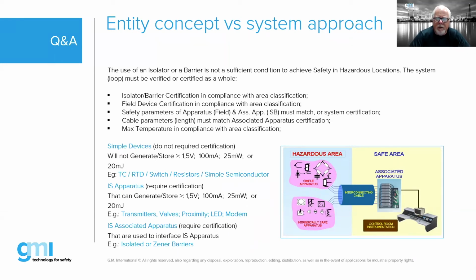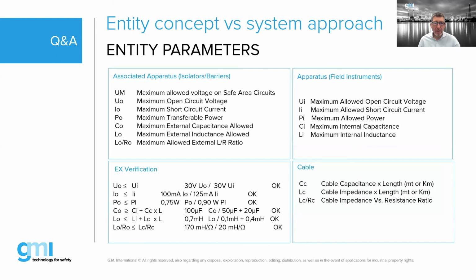The barriers they were using, GMI products, are rated to be installed in a zone 2 area. So if you ever run into that situation where the cable length between the associated apparatus and your field device is just too long based upon the gas group, that's certainly one potential solution. In fact, we have a couple of questions regarding this, which we have prepared answers to. Okay. So basically, guys, you have to check the parameters, and let's see if I can move forward like this.